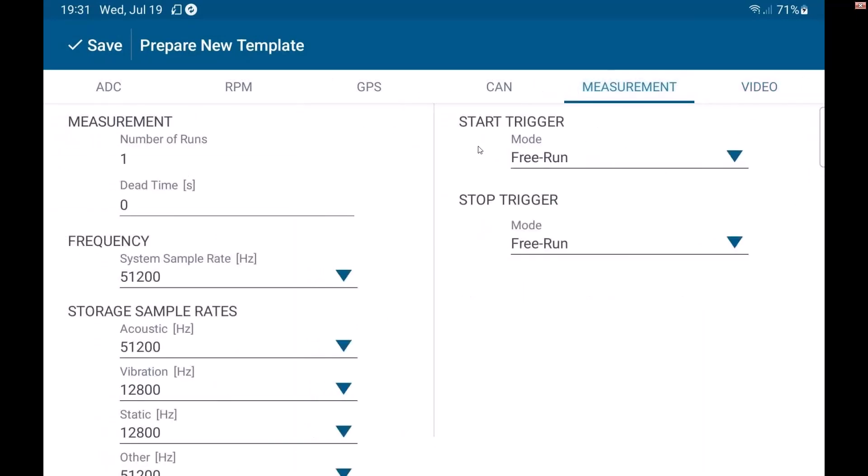In measurement settings, I have everything available to me here where I can do multiple sample rates based on channel groups. You can see my vibration, static and other channel groups. I can set all that up. I can do triggers as well as the duration and everything I need to do.